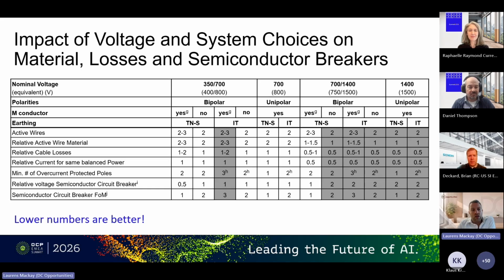Then if you look at relative losses, we have a similar picture that obviously also if the voltage goes higher, the losses go down. Here we assume the same current density in the conductor. So that's why if the voltage doubles here, the losses kind of halve. Obviously, if you would use the same conductor material, so if you don't take the savings in the line above, then you would only get a quarter of the losses. But basically, in this case, we distribute the benefits of the higher voltage, half to the losses, half to the material savings.